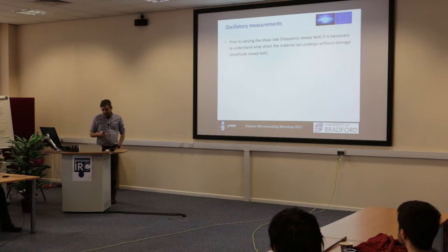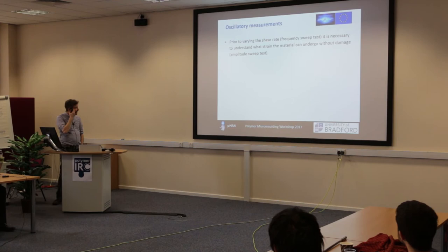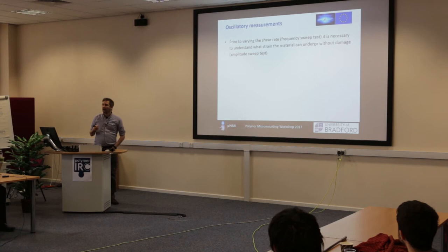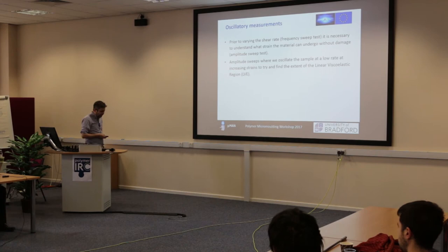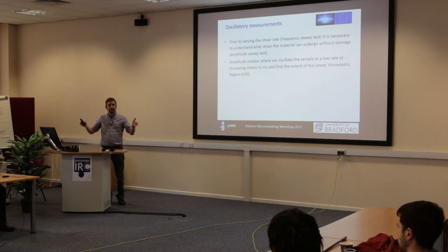Instead of looking at these simple flow curves, looking at the oscillatory tests, okay, in order to do these, we need to know what the maximum strain we can operate at is, okay? I.e., we need to establish this linear viscoelastic regime. We need to find where it breaks down, okay? And so what we do is what's known as an amplitude test, amplitude sweep. Basically, we run a range of strains and we look at the behavior of the storage modulus and see when it starts to break down, okay?